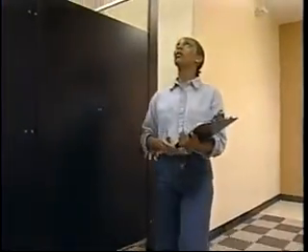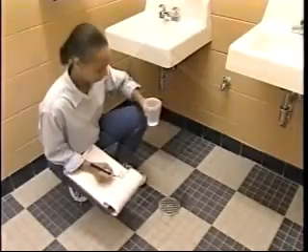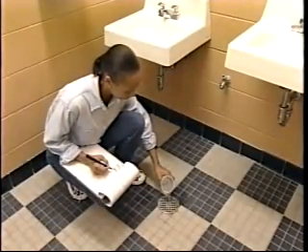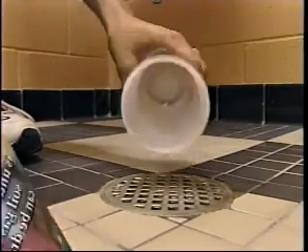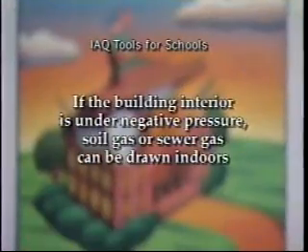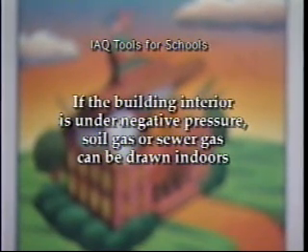I'll go to the kitchen area and check the combustion appliances. I'll check the bathroom and maintenance supplies, and I'll meet you in the hallway. When checking the bathrooms and general plumbing areas, make sure that the exhaust fans are operating. Be sure that all drains have traps and are filled with water. Drain traps can cause IAQ problems when water in them evaporates due to infrequent use. If the building interior is under negative pressure, soil gas or sewer gas can be drawn indoors through a dry drain trap.